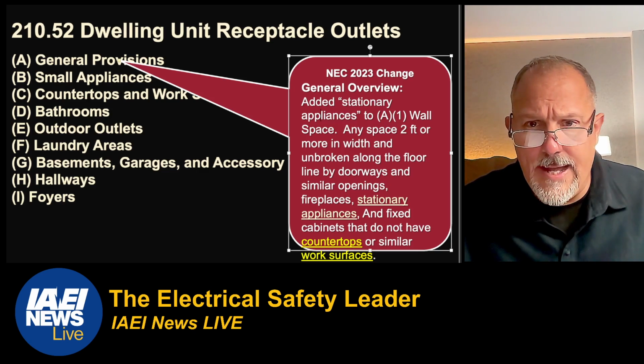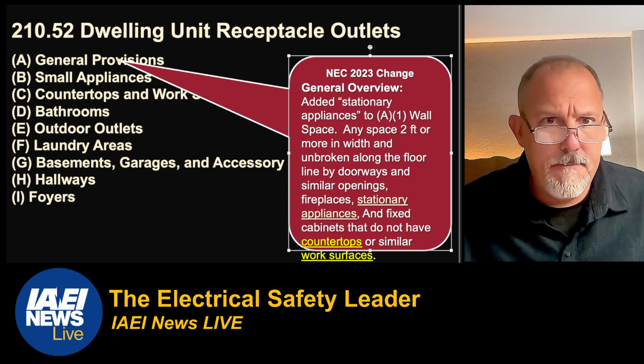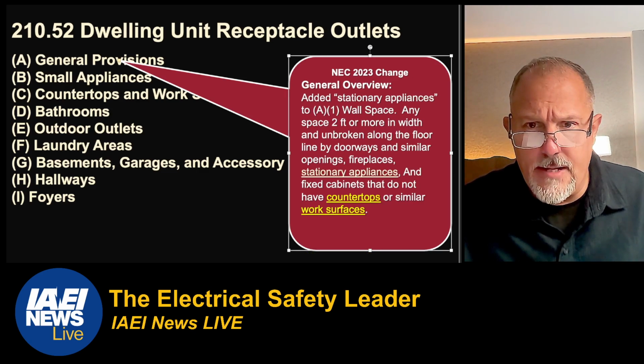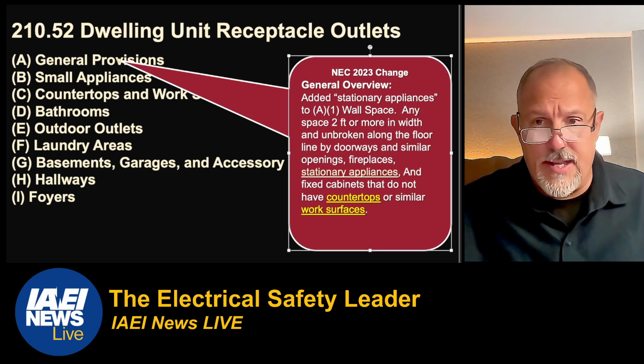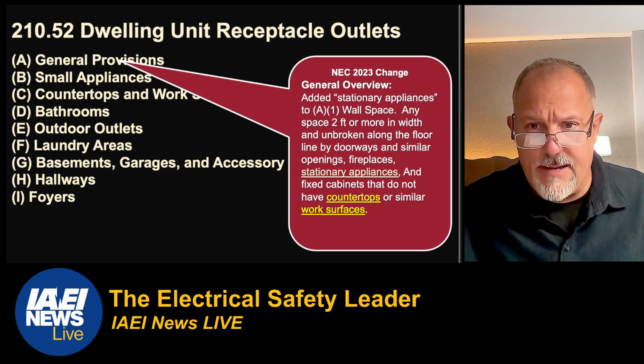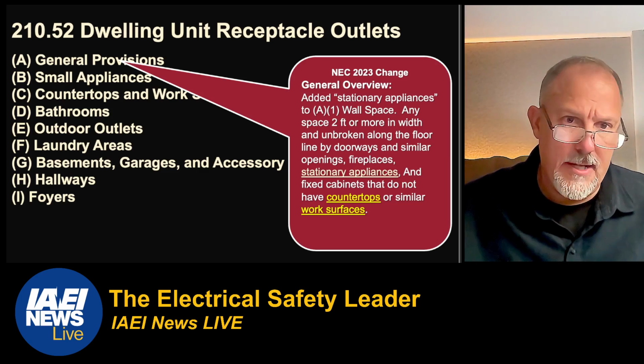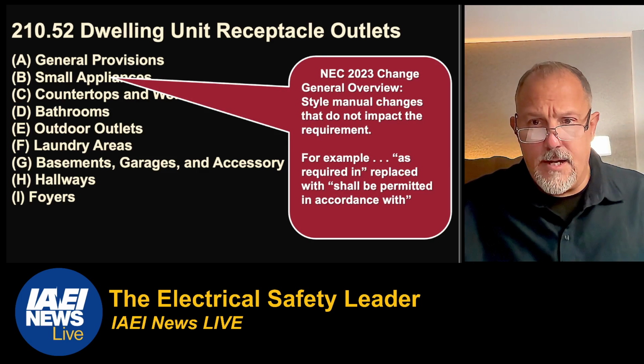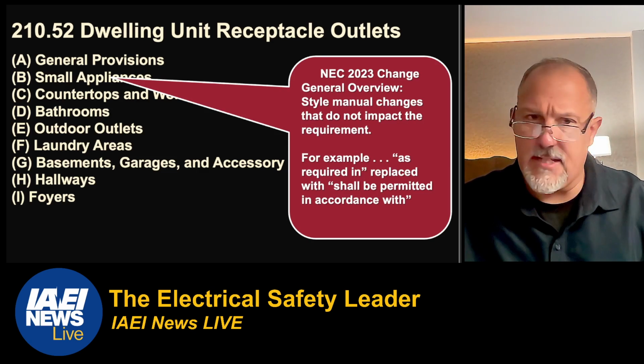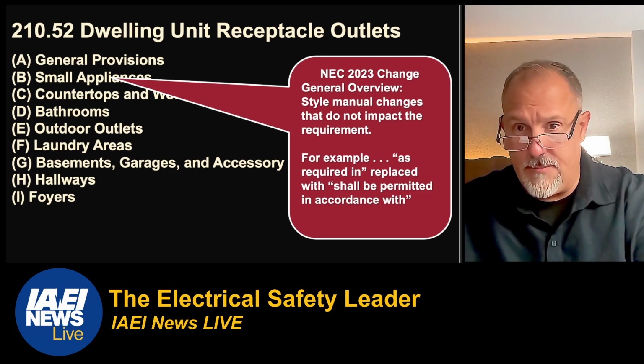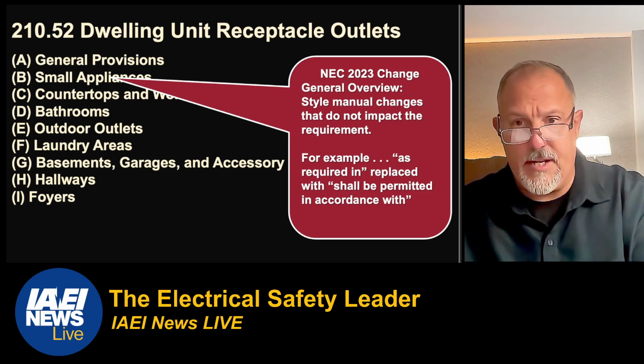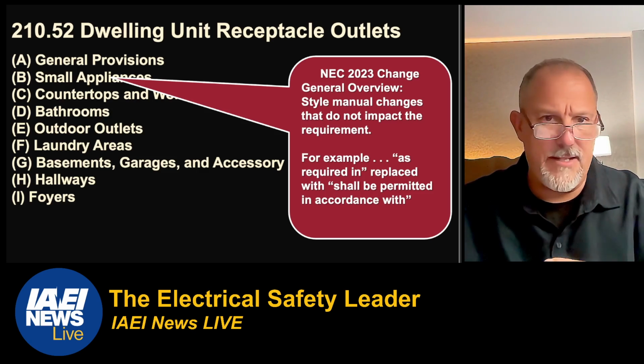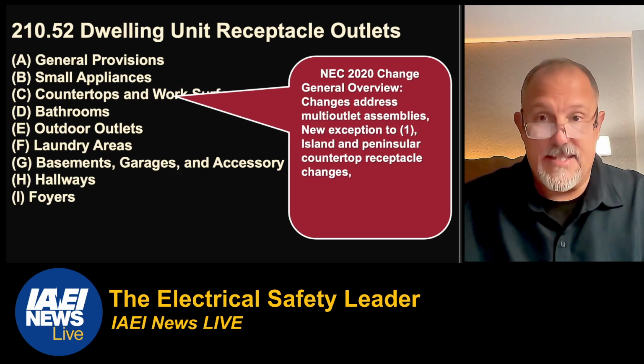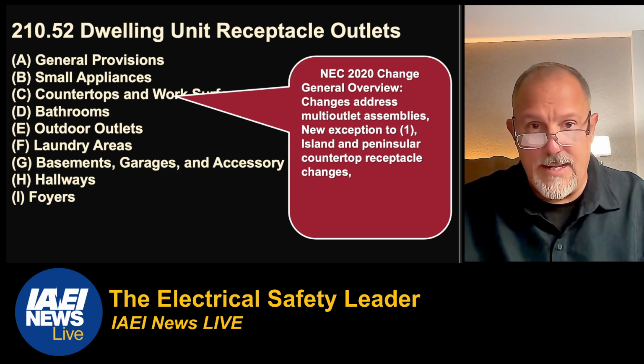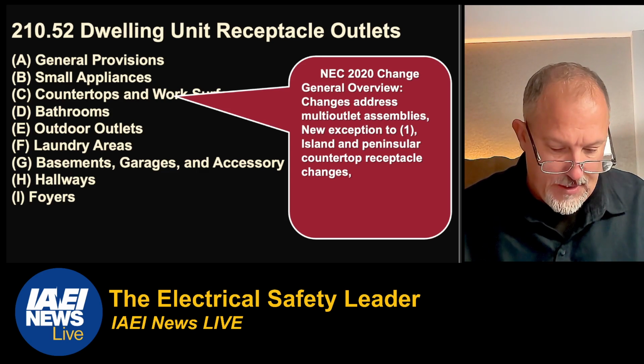Let's just talk real quick. So they added stationary appliances: wall space, any space 2 foot or more in width, fireplaces, stationary appliances. They also added fixed cabinets that do not have countertops or similar work surfaces. That's general provisions. And in B, they just did some style manual cleaning up, not a big significant change. For example, "as required in" is replaced with "shall be permitted in accordance with." So they're not changing the intent. So B is pretty much the same. C, so island and peninsula. So here's what we did in 210.52(C).